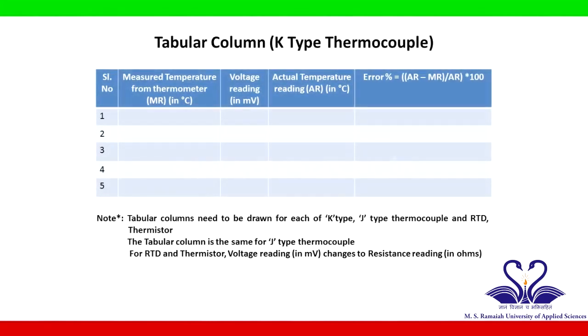The tabular column needs to be drawn as shown for a K-type thermocouple. It has to be noted that 4 separate tabular columns need to be drawn, one each for K-type thermocouple, J-type thermocouple, RTD and thermistor. The tabular column for J-type thermocouple is the same as the one drawn for K-type thermocouple. For RTD and thermistor, the voltage reading in the tabular column is to be replaced with resistance readings.